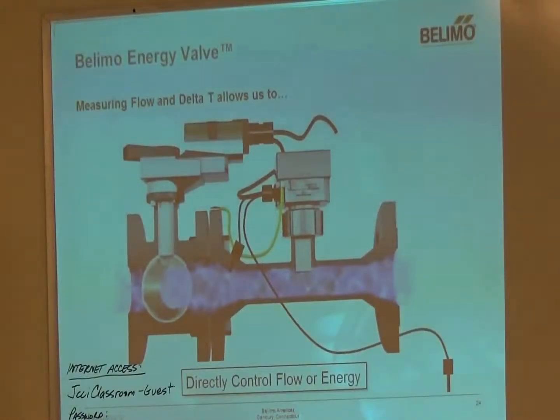So, because we're able to measure flow and delta T, that allows us to directly control based on your flow or your energy. So what are we saying here? Well, when we're talking about the flow, the valve will get its control signal from your building automation system, as usual. It sees that control signal as a request for a certain amount of flow, a certain amount of GPM. Then the sensor can sense if, for example, some other valves close, it gets an increase in pressure. The sensor will identify an increase in flow starting, and then it will adjust the valve position so you maintain the same flow because you haven't changed your control signal at all. It's just an increase in pressure or decrease in pressure, either way, that's caused a change in what the sensor is seeing.